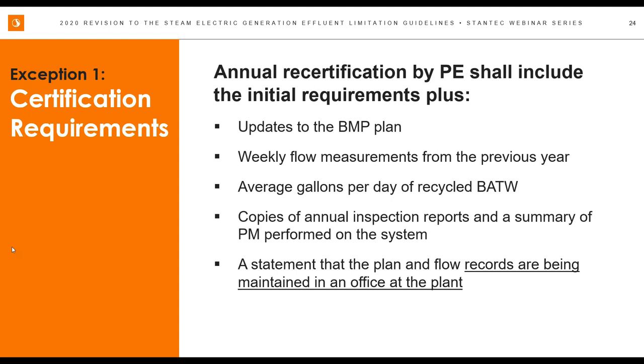Annual recertification by the PE shall include not only what the initial requirements were on the previous slide here, but also any updates to the BMP plan, weekly flow measurements from the previous year, average gallons per day that were recycled, copies of the annual inspection reports, and a summary of preventive maintenance performed on the system.